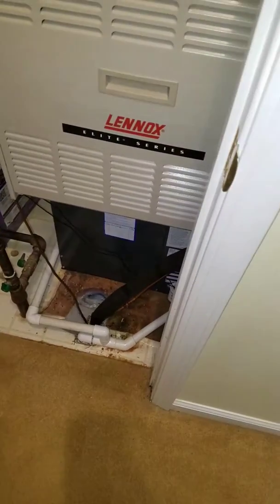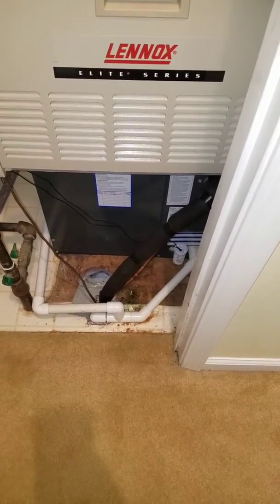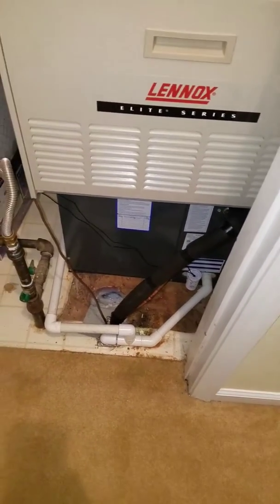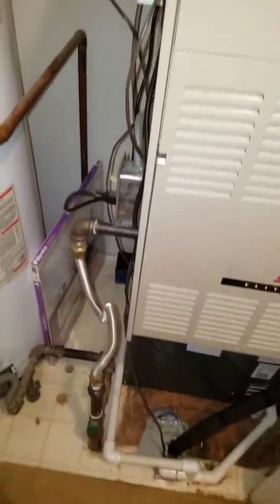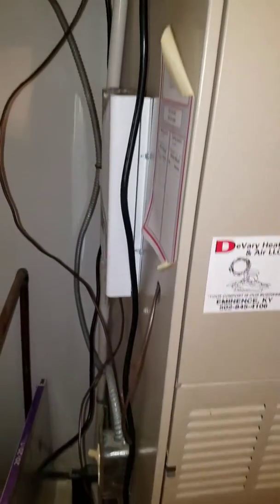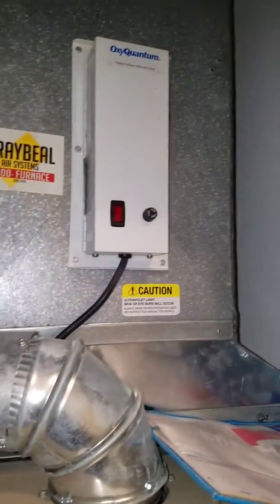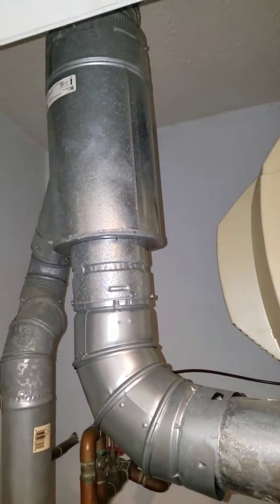Hey guys, this is the Helena Krur Residence and we put in a 3-ton ASX14 on this system. We have an issue now with the current furnace that's in — with the heat exchanger. Because of the corrosion that's blown out of that heat exchanger, the furnace is in danger of putting carbon through the ductwork. So we are looking at possibly replacing the furnace.